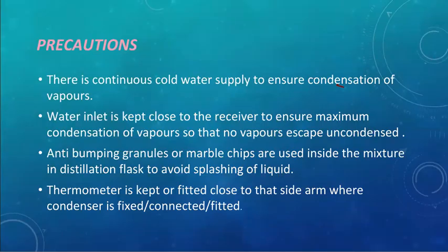Let's have the recap of the precautions which I have mentioned. A few of them are here and I'll be adding the rest over here. There should be a continuous cold water supply to ensure the condensation, and the cold water needs to enter from the lower end, which is close to the receiver, right?